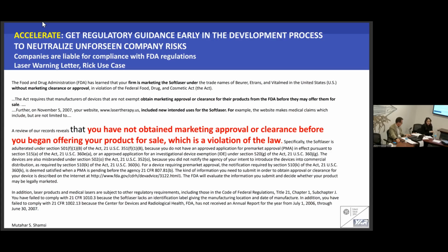In cases where there are key differences, because this is an area where I see a lot of people run into issues with FDA, is, hey, our mechanism is slightly different, but the plastic is the same and it's doing the exact same thing and it's intended for the exact same population. If that change that you have made in the product, whether yours is larger or smaller or thinner, and from FDA's perspective, you have to prove to them that that difference isn't introducing a significant impact on the safety profile of that device or the effectiveness of that device.